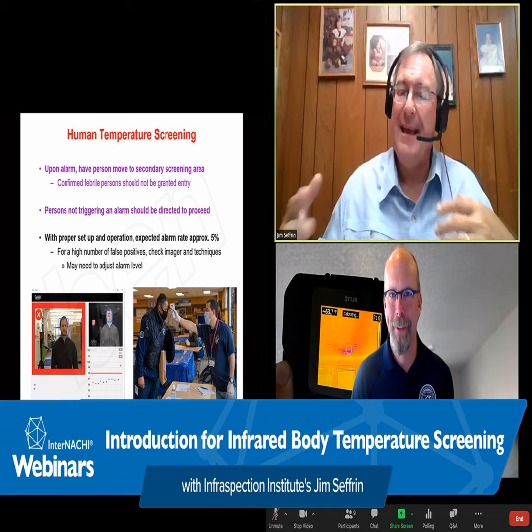Under the standard published by the International Organization for Standardization, which goes by the abbreviation ISO, ISO's technical report 13154:2017. I want to point this out to those watching today. Note the date on the screen, 2017. This is not a new document. It's been around as of this year for 3 years, and it was predated by others that date back to the early 2000s. So, under medical electrical equipment, deployment, implementation, and operational guidelines for identifying febrile humans using a screening thermograph. This is where we find a lot of the protocols that were set up subsequent to the SARS outbreak that occurred back in 2003.